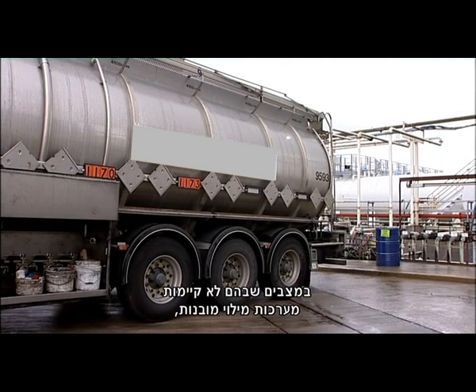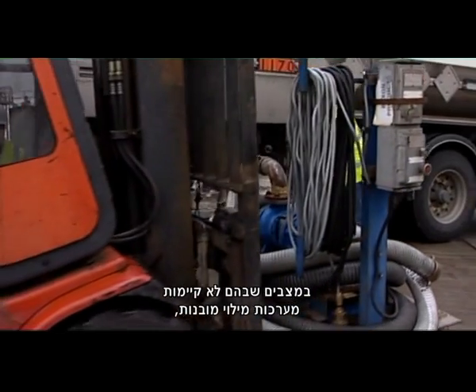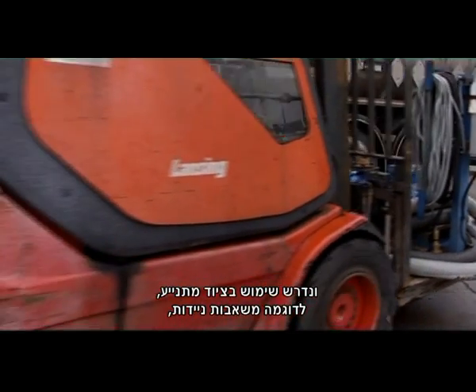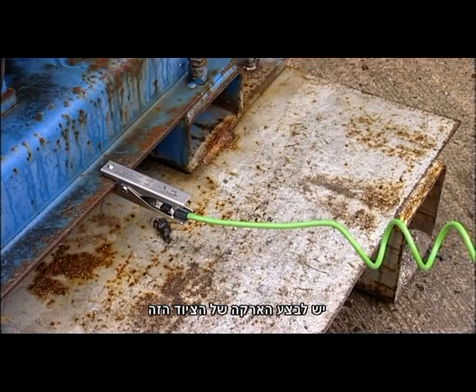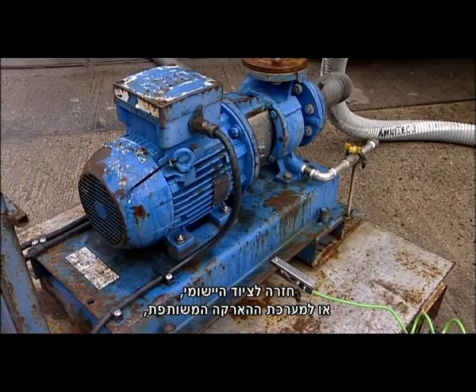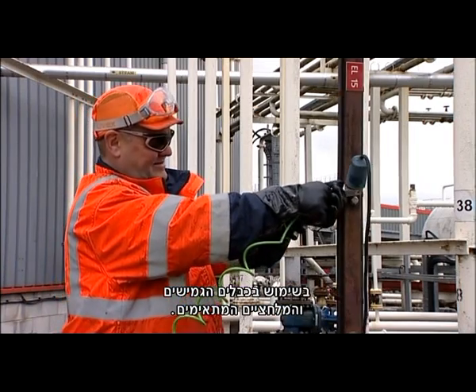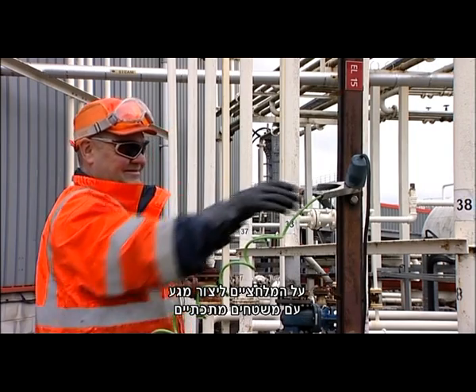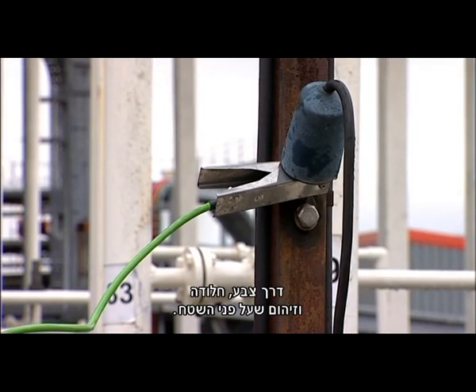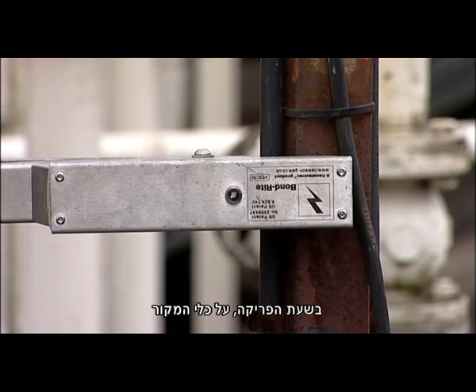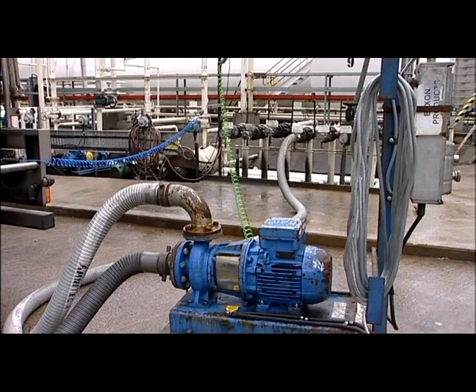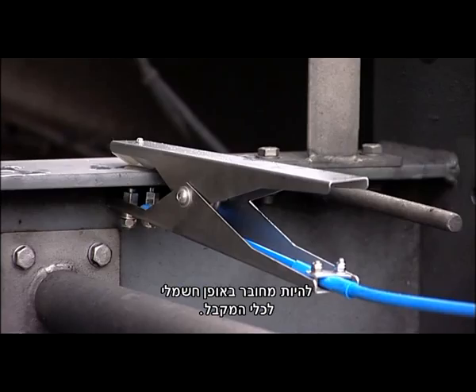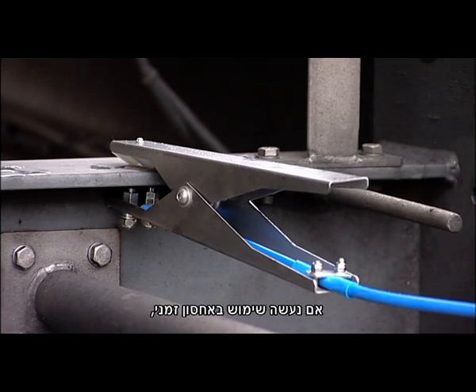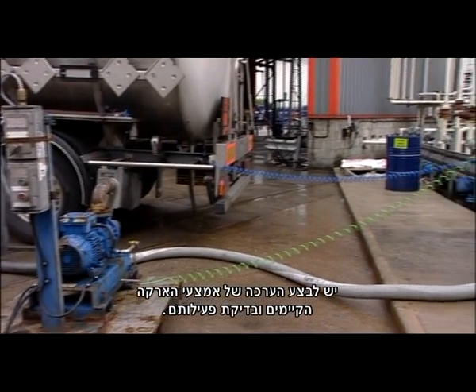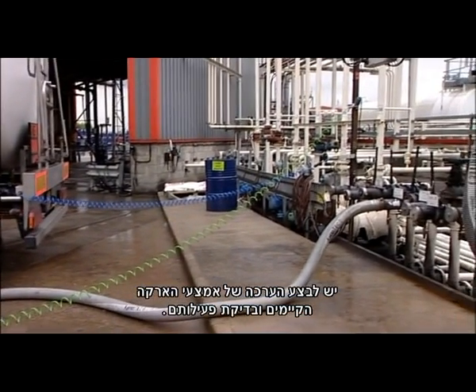For situations where permanently interlocked filling systems are not provided and the use of portable equipment is required, for example mobile pumps, this equipment must be earthed back to the process equipment or common earthing system using the appropriate flexible cables and clamp. The clamp must make contact with metal surfaces through paint, rust, and surface contaminants. When discharging, the source vessel should be electrically connected to the receiving vessel. If temporary storage is used, an assessment of earthing provision and associated earth testing should be carried out.